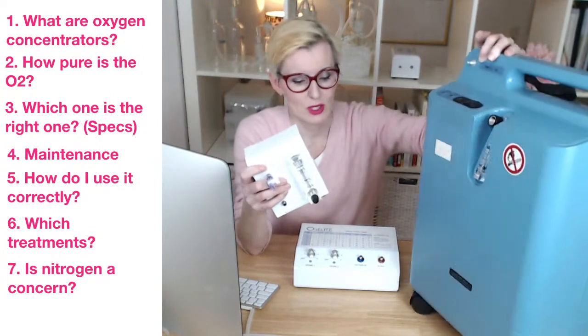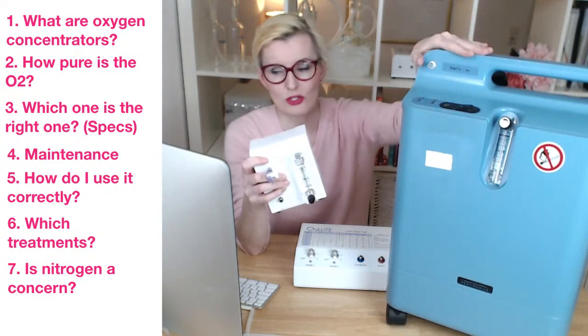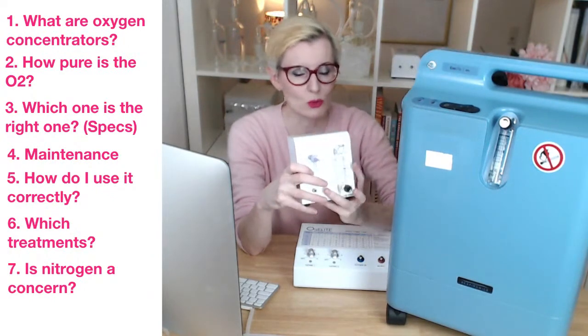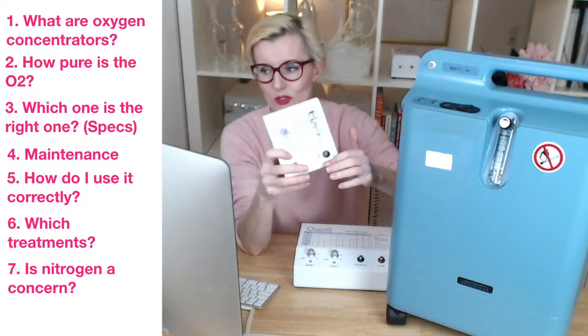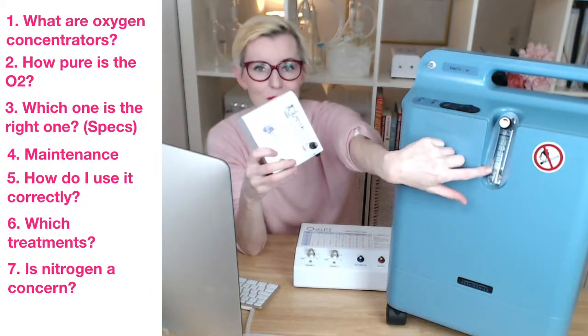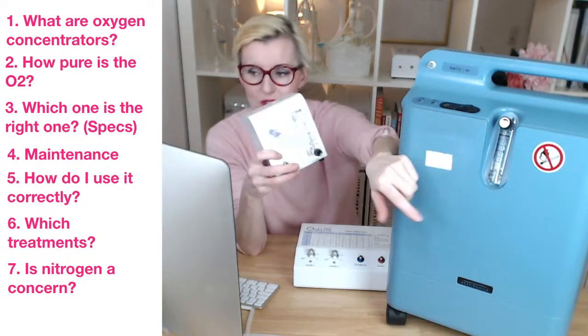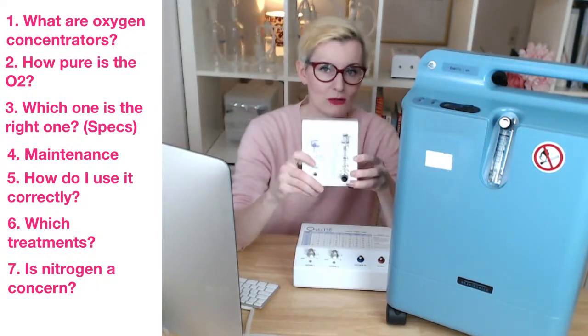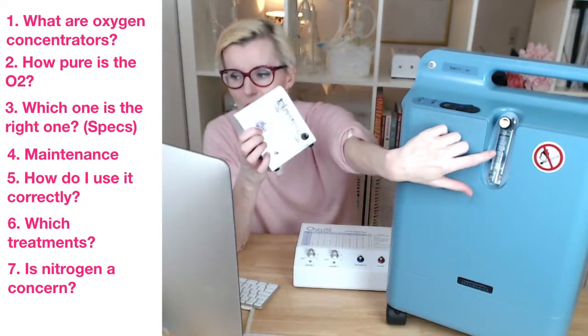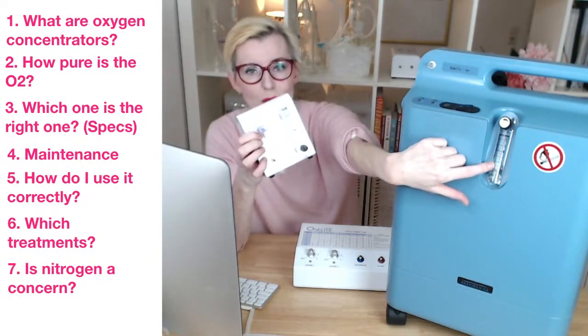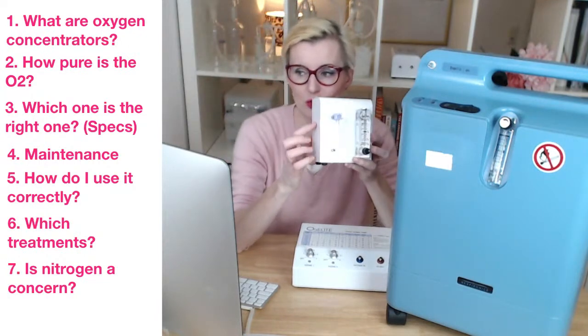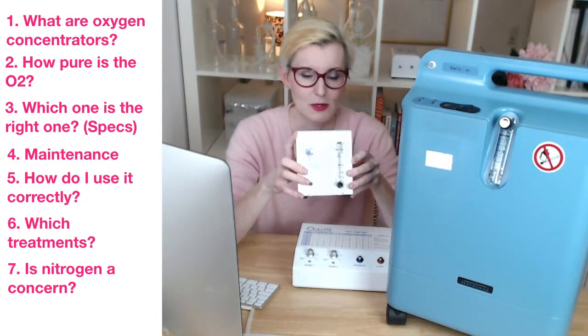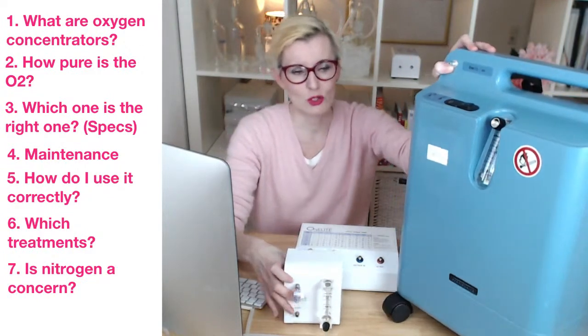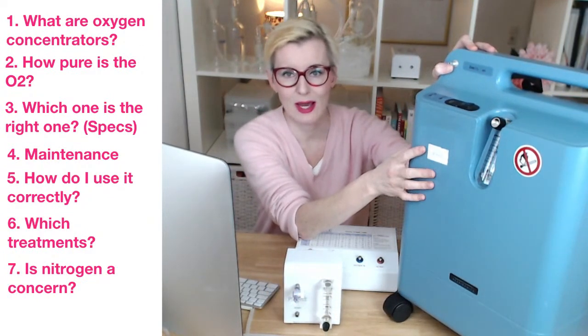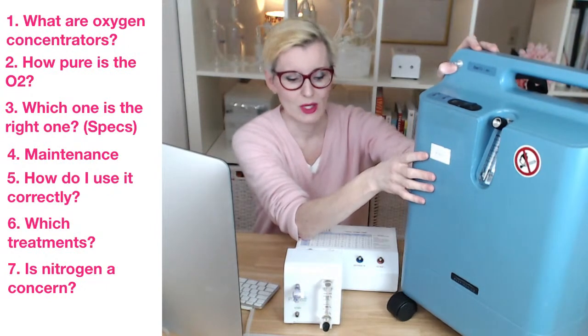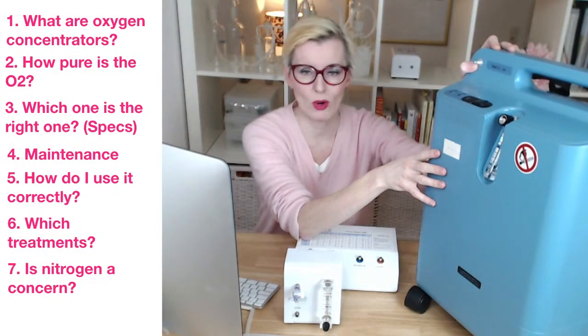Okay, because basically, when you have an oxygen concentrator, you will be dealing with two different regulators. One regulator is the built-in regulator in the machine, this thing here, and the other is the external regulator, right? This built-in regulator has to be set at 2 liters per minute in order for this external regulator to work properly. At 2 liters per minute, your machine has to produce at least 90% pure oxygen. And so this is important. Those are one of the specifications.